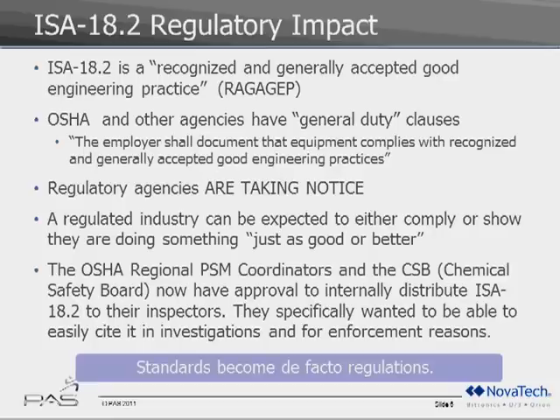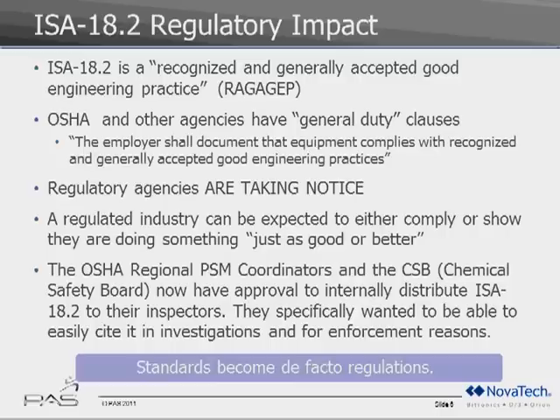As far as the regulatory impact of 18.2, regulatory agencies have a general duty clause and interpretations. For example, OSHA 1910.119, subsection D.3.2, states the employer shall document that equipment complies with recognized and generally accepted good engineering practices — called RAGAGEP. There is little question whether 18.2 is an example of RAGAGEP, and companies should expect regulatory agencies to take notice.